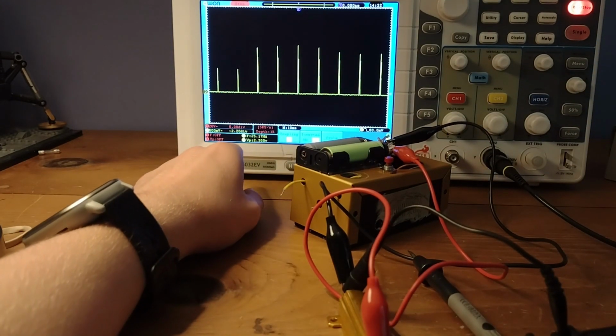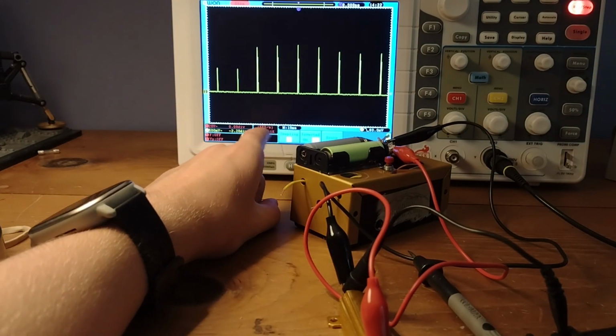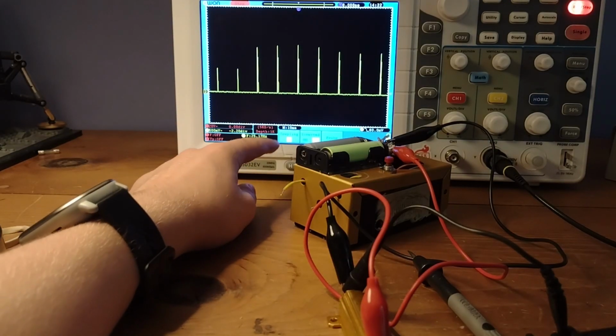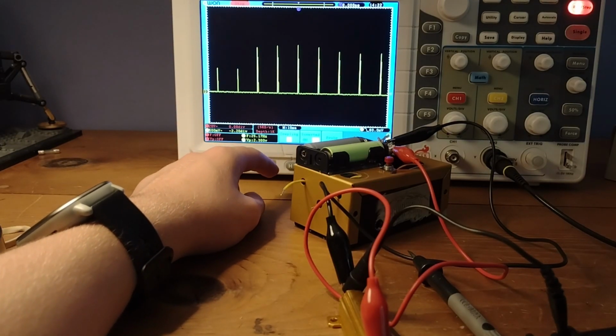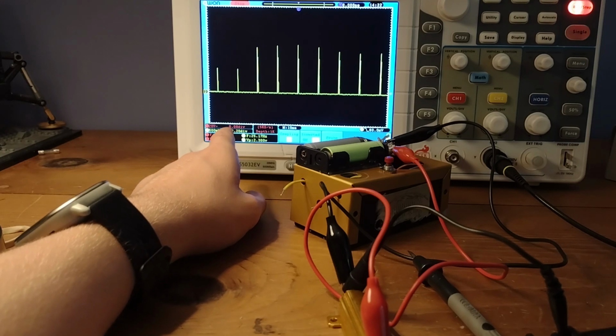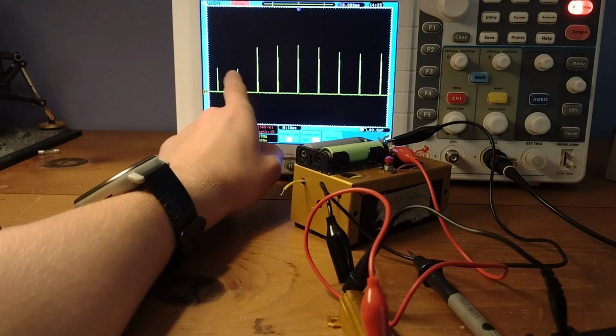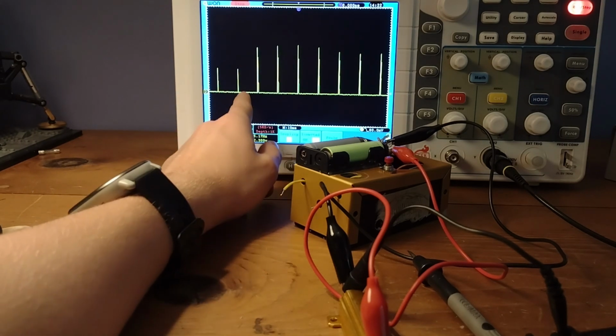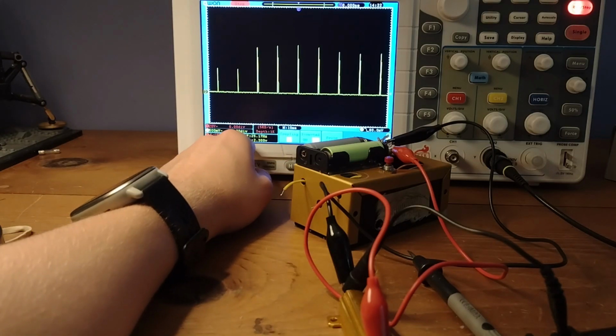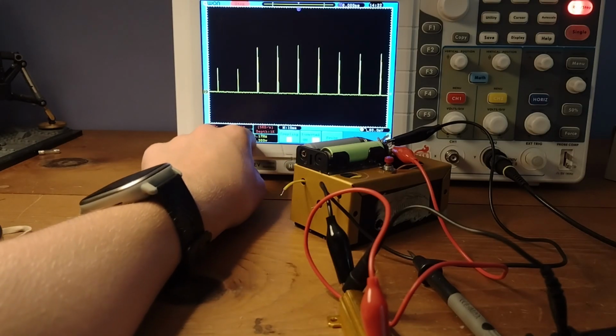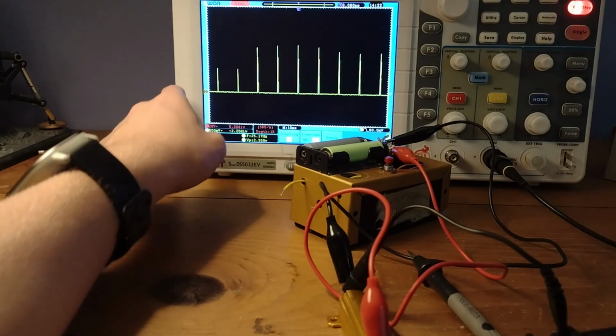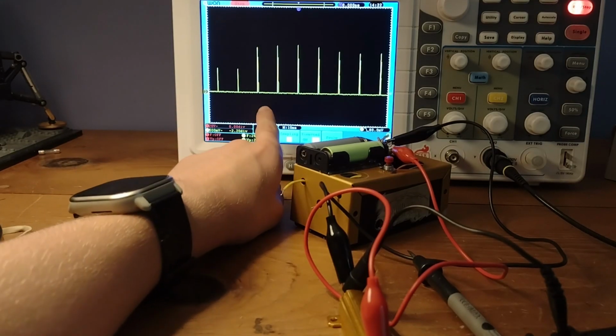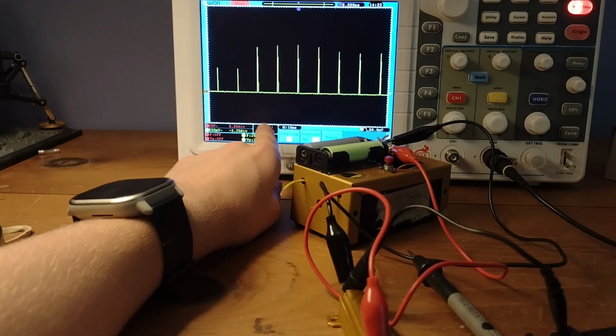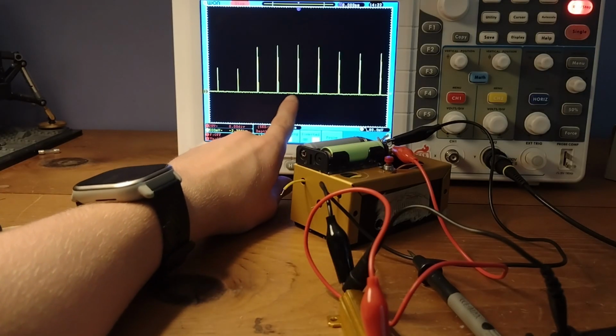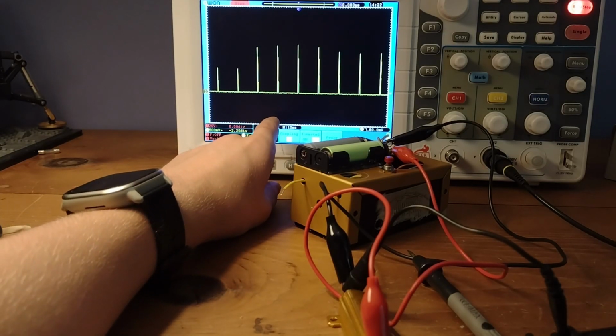These are the current spikes from when the relay is switching, and these happen because the relay has a coil in it, and when that coil switches, it draws some current, and whenever it draws current, there's a spike on the meter. These are about 2.3 volts peak, so it actually draws about 2.3 amps immediately when the relay switches, but because these pulses are very short, the fuse doesn't have enough time to heat up and blow open.